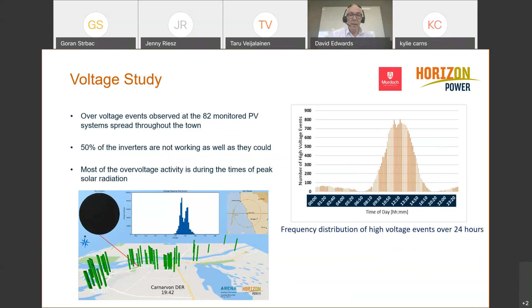You can see that the number is quite high, and this is a problem, as Jenny just mentioned, that's becoming apparent nationally and internationally as solar and PV penetration increases. Here in Australia, there's been a great deal of discussion around using inverter control at a primary level by adjusting response curves and settings within the inverters themselves. So we started to explore how we could use reactive power droop curve settings to manage network overvoltage events. And what we discovered was unexpected and initially very surprising and interesting, but at the end of the day, it's quite obvious, and I'll explain why in the following slides.